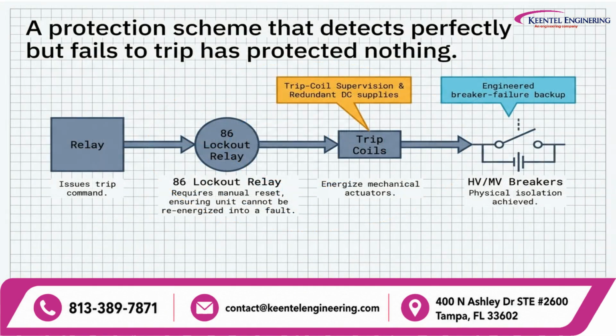Here is one of the most important principles in protection engineering. A protection scheme that detects a fault perfectly but fails to trip has protected nothing. The sequence begins with the relay issuing a trip command. That command may operate an 86 lockout relay. The lockout relay provides an important layer of security and control. It can require a manual reset, ensuring that the transformer cannot simply be re-energized into the fault. The next step is energizing the mechanical trip actuators. Finally, the high voltage or medium voltage breakers must physically open and isolate the transformer.